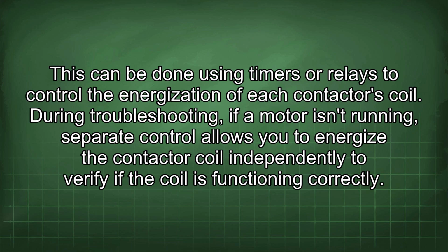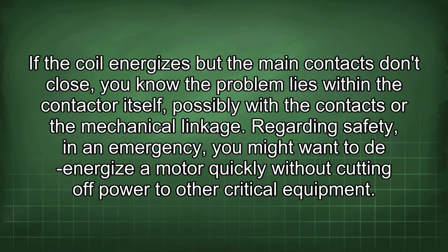During troubleshooting, if a motor isn't running, separate control allows you to energize the contactor coil independently to verify if the coil is functioning correctly. If the coil energizes but the main contacts don't close, you know the problem lies within the contactor itself, possibly with the contacts or the mechanical linkage.